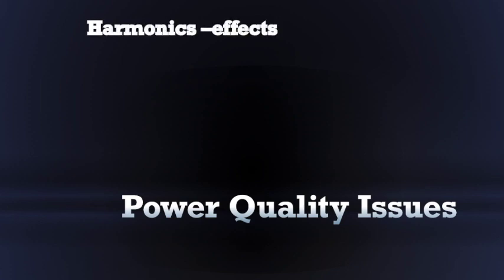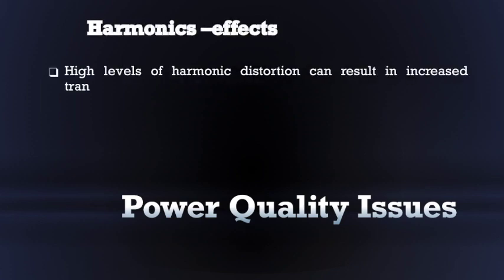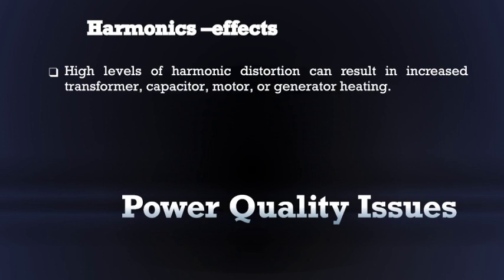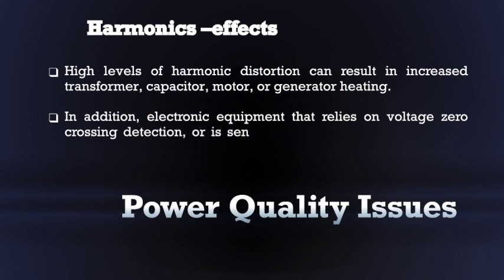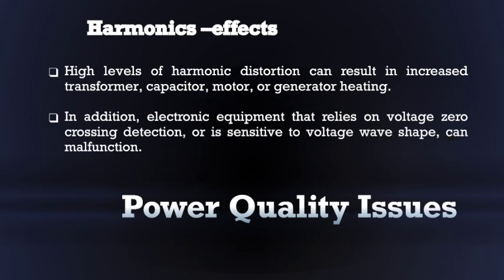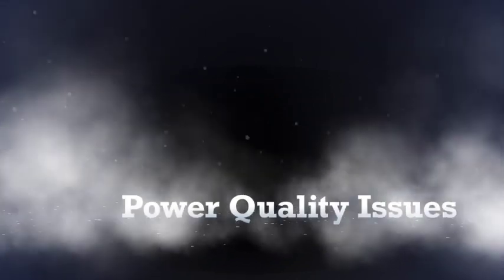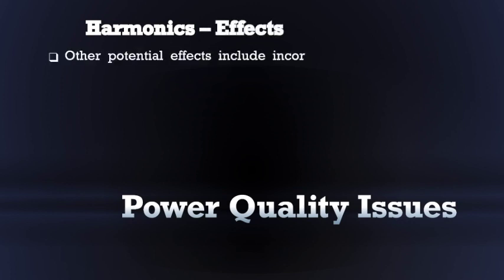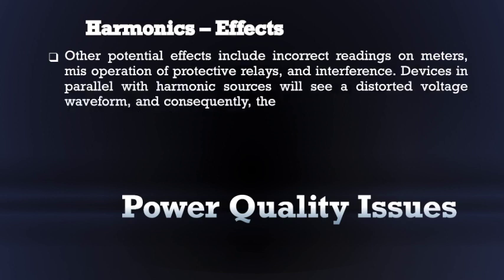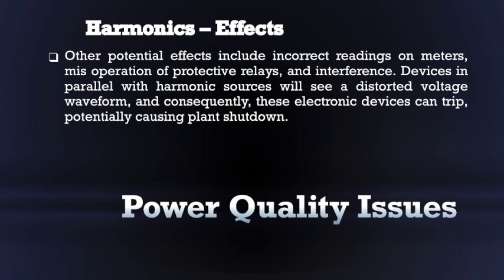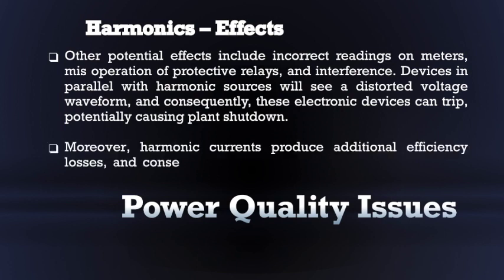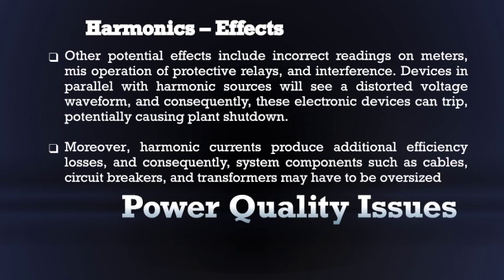Now we will see what are the effects of harmonics. High levels of harmonic distortion can result in increased transformer, capacitor, motor or generator heating. Electronic equipment that relies on voltage zero crossing detection or sensitive to voltage wave shape can malfunction. Other potential effects include incorrect readings on meters, misoperation of protective relays and interference. Devices in parallel with harmonic sources will see a distorted voltage waveform and consequently these electronic devices can trip, potentially causing plant shutdown. Also, harmonic currents produce additional efficiency losses and consequently system components such as cables, circuit breakers and transformers may have to be oversized.